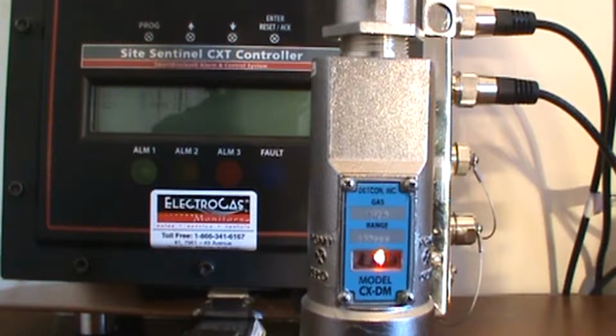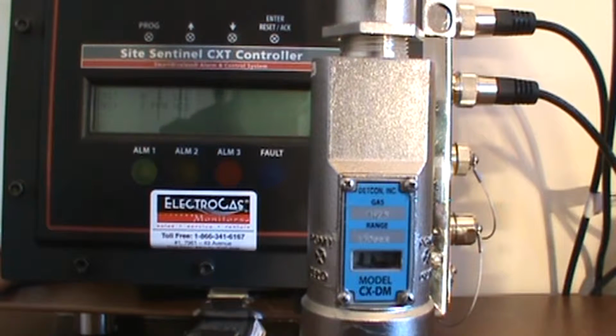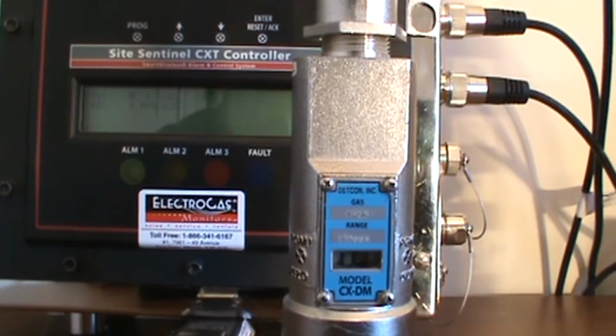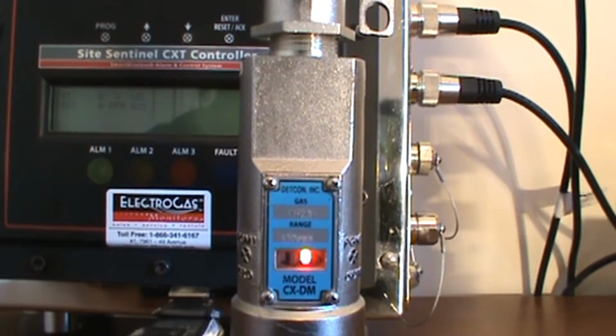Before we perform a full function bump test, we must warn all workers in the area that we're performing this test. Otherwise, we could create a mass evacuation. The second way to perform a bump test of this sensor is using the onboard menu on the sensor. To access the onboard menu of your CXDM sensor, you simply hold the magnet to the Program 2 side of the sensor and hold it there until an arrow first appears, and without letting it go, holding it until the arrow disappears to access the menu.